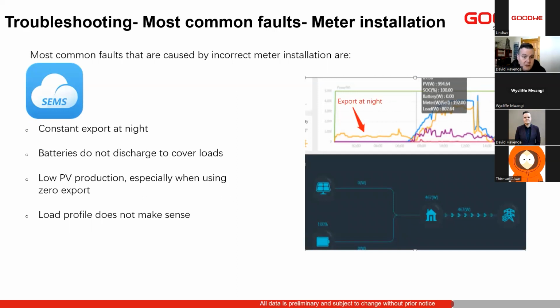If the meter is not installed correctly, we will see a lot of strange data: constant export at night, our batteries remaining full and not discharging to loads, and the load doesn't make any sense. If we do have any installation issues with the meter, then this might be the cause. It's very important to verify on the SEMS portal after your installation. I know we do have the meter test, and you can run it. It does work in certain scenarios, but sometimes the meter test is unable to accurately judge CT direction or CT placement. So we always verify this on the SEMS portal.